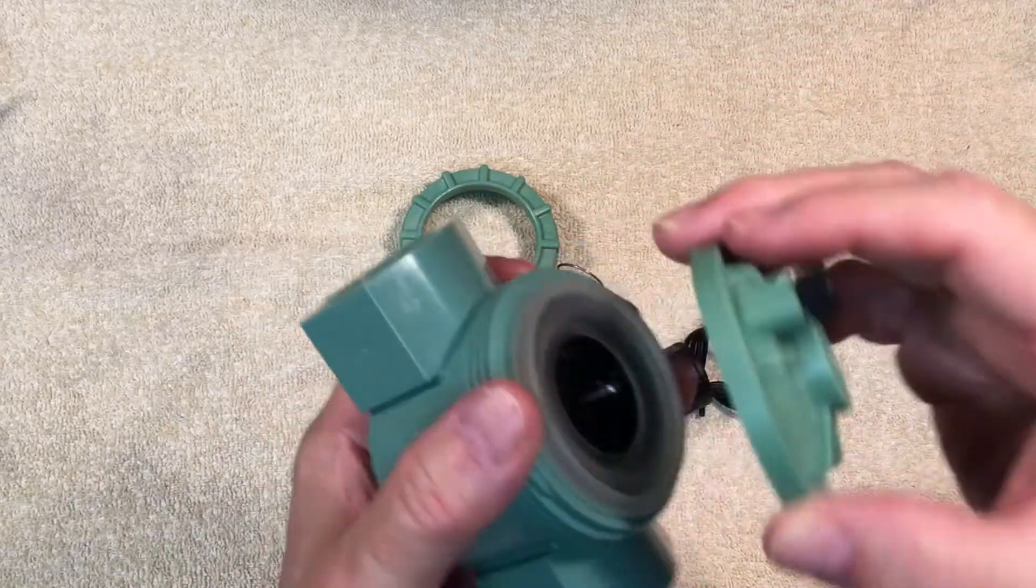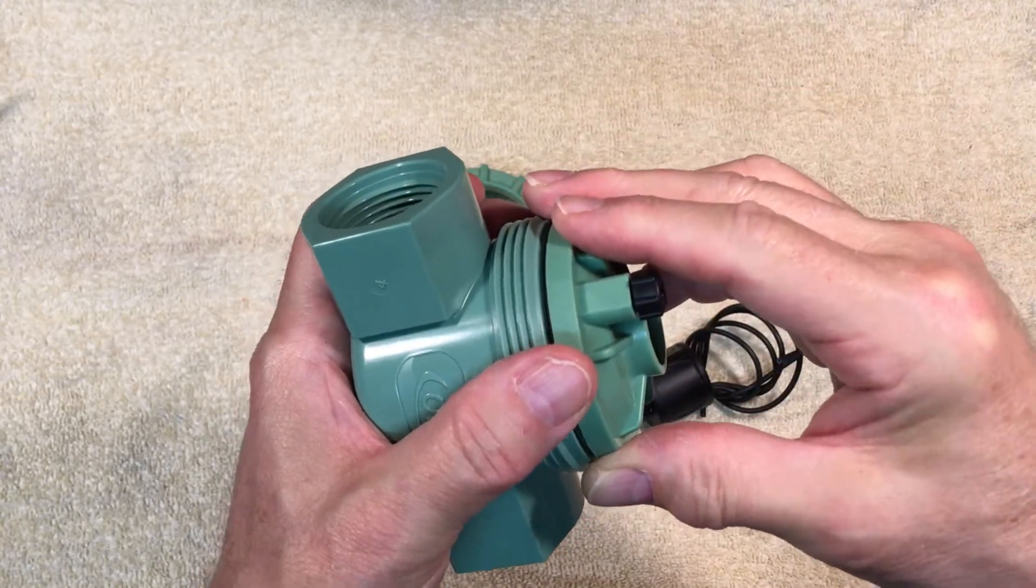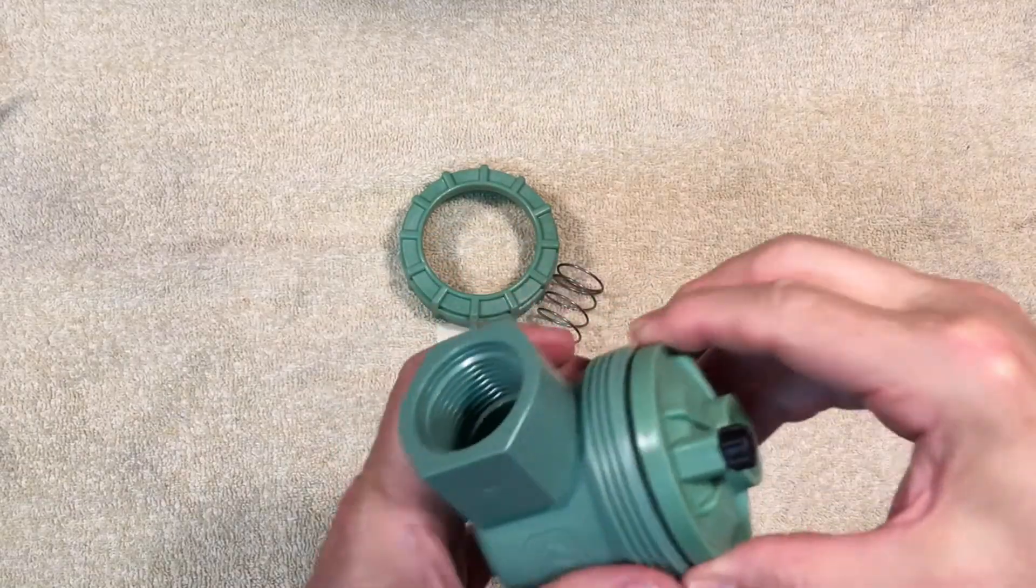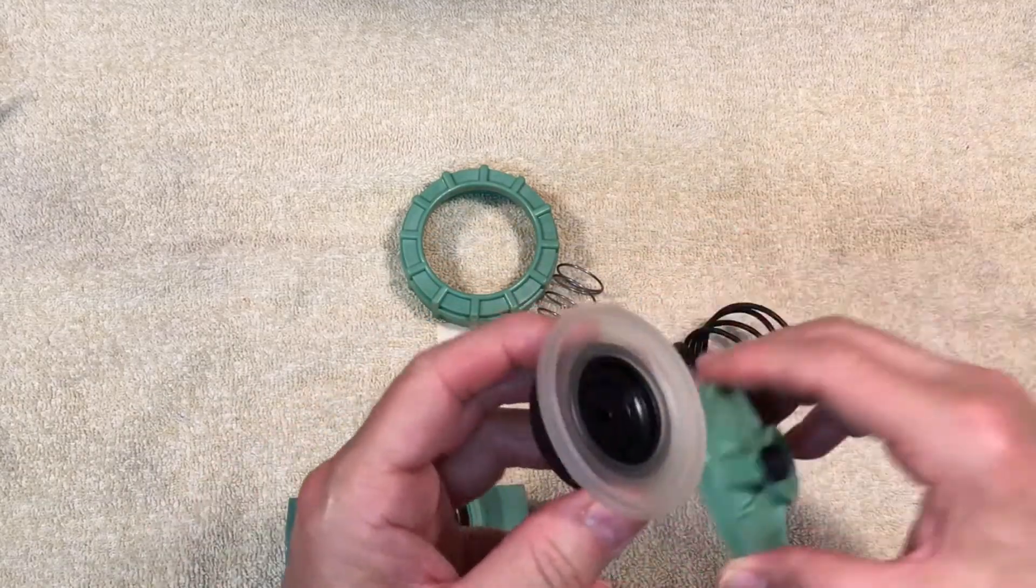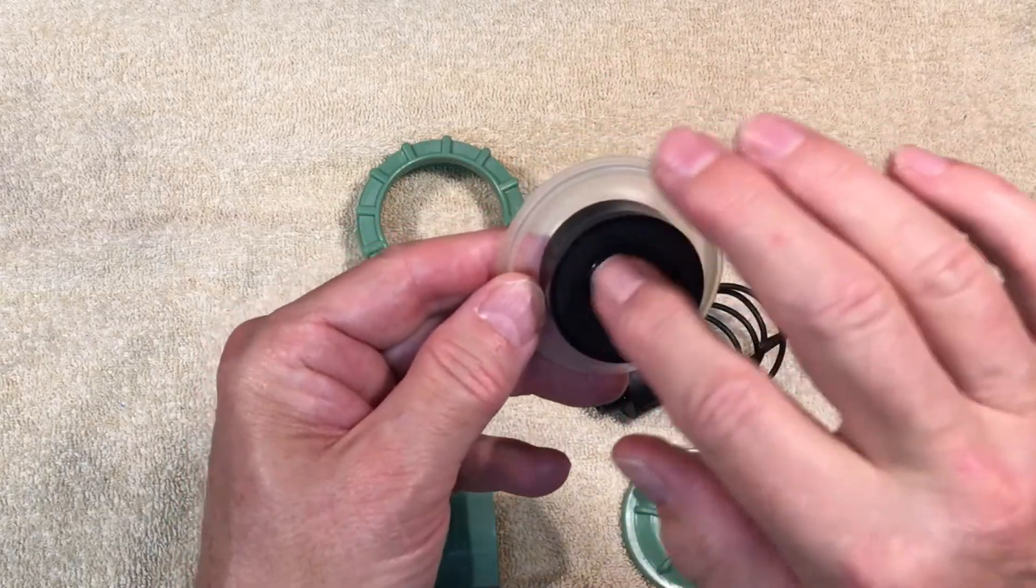That water in the top of the valve, above the diaphragm, exerts pressure from the top to keep the diaphragm pushed down or closed. The top of the diaphragm is larger than the bottom of the diaphragm, so there is more water pressure to bear on the top, keeping it down tight.